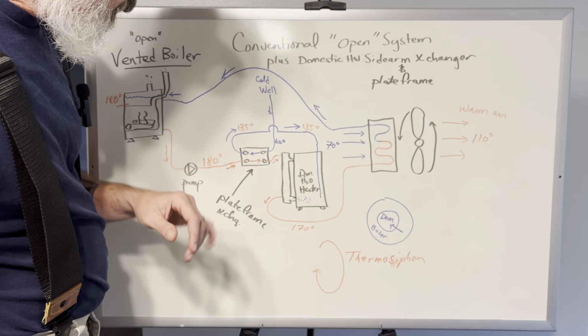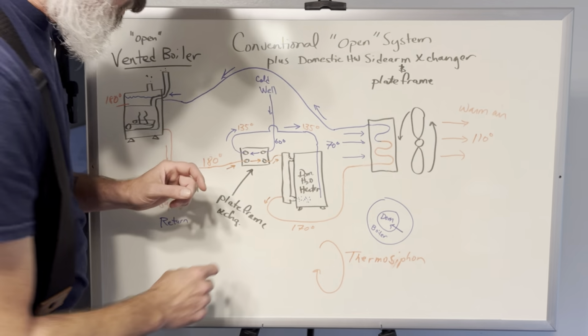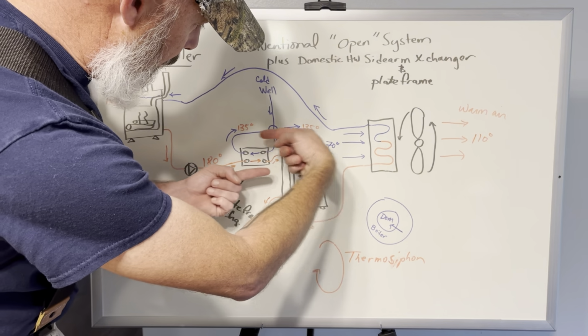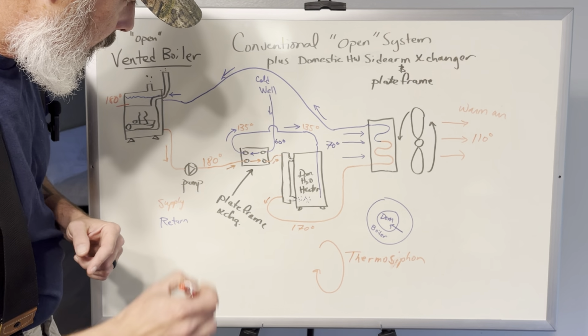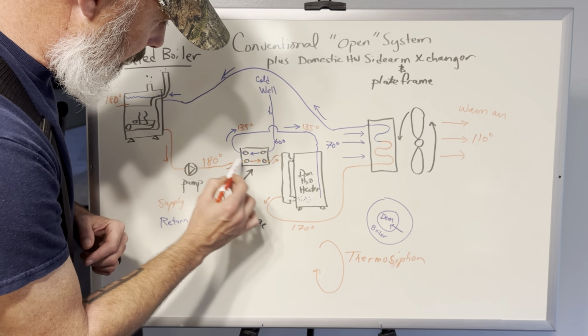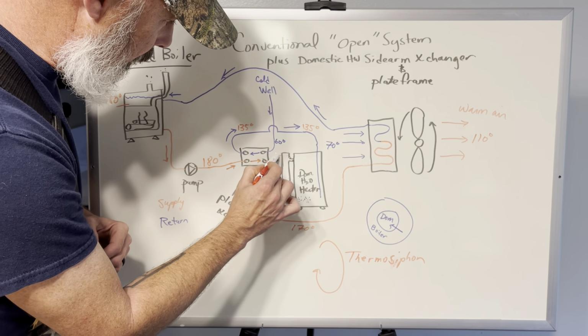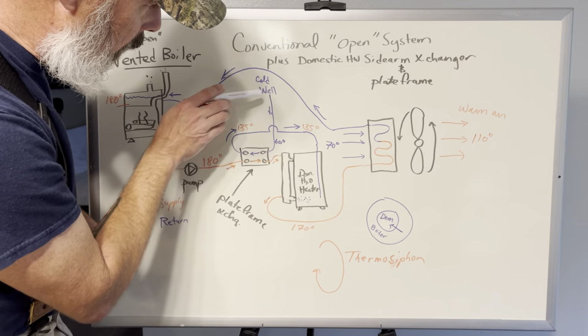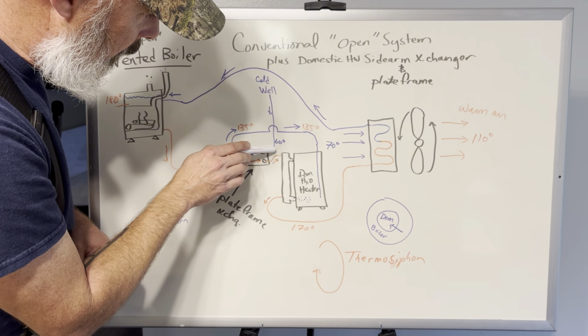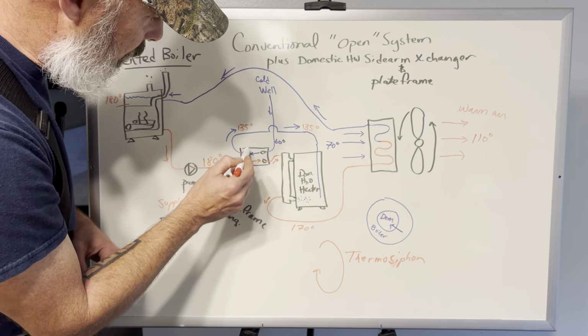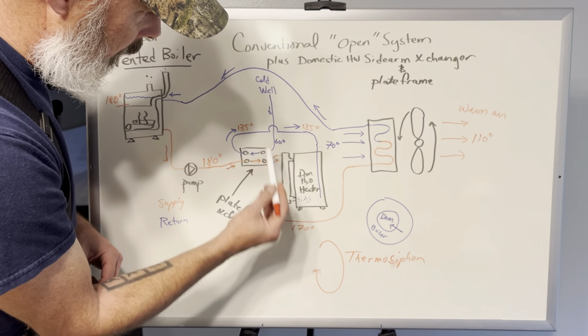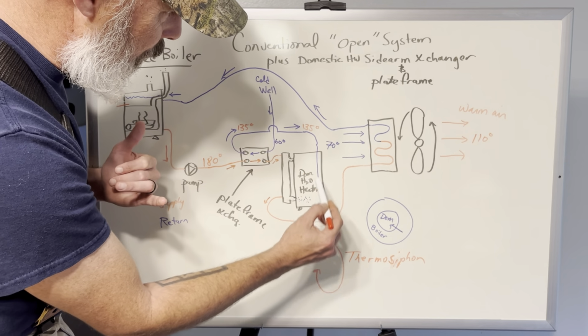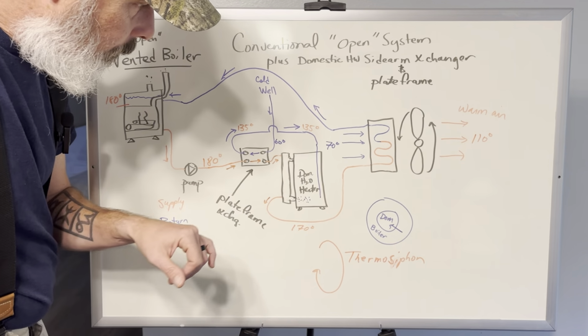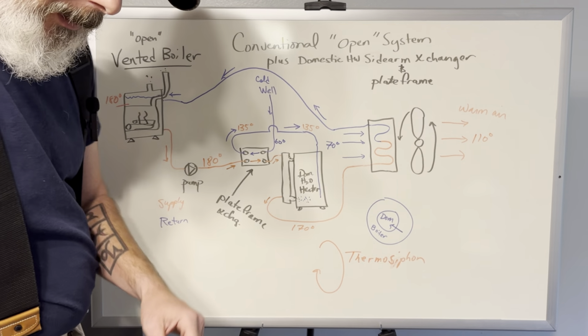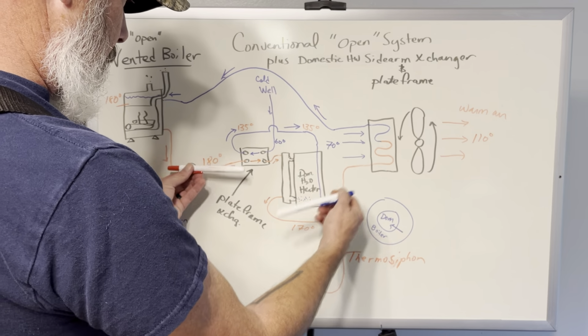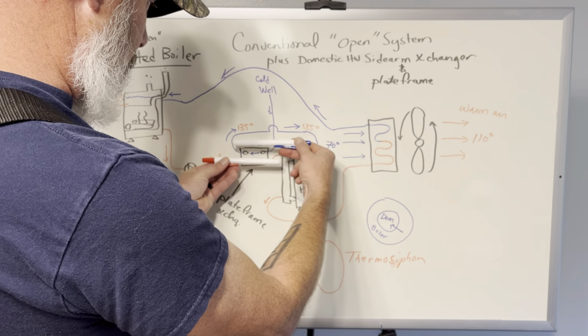But so how this works, I tried to draw it like this because I wanted to really drive home this whole concept of counterflow. So the boiler water would come in here, and it would go through the heat exchanger and come out here and continue on its way. Whereas the cold water from the well would come in here, go into this side of the heat exchanger, pass through, and come out and go, sorry, I had to cross that line, but it basically would go into the cold inlet of your water heater. Now, so you see we have counterflow, always counterflow. The hot water is going this direction, the cold water from the well is going that way.